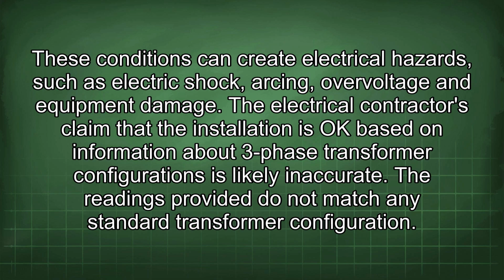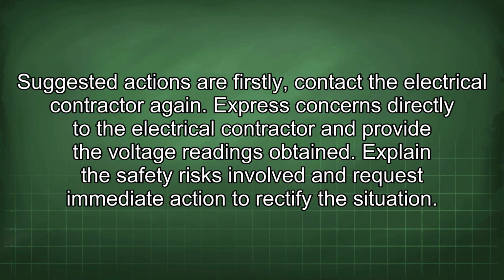The electrical contractor's claim that the installation is okay, based on information about three-phase transformer configurations, is likely inaccurate. The readings provided do not match any standard transformer configuration. Suggested actions are: firstly, contact the electrical contractor again. Express concerns directly to the electrical contractor and provide the voltage readings obtained. Explain the safety risks involved and request immediate action to rectify the situation.